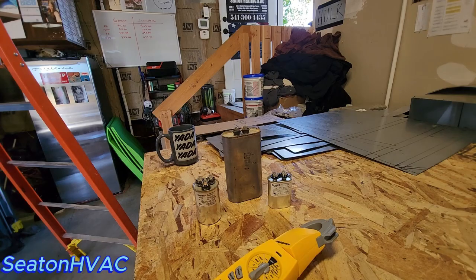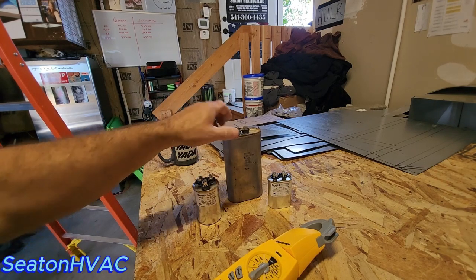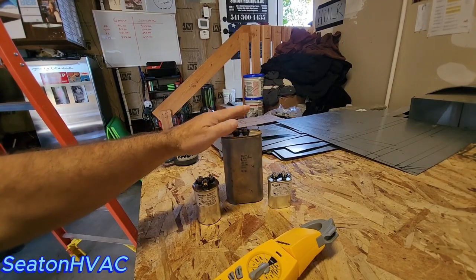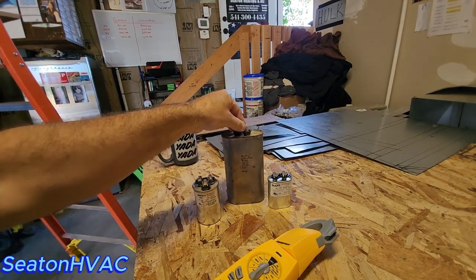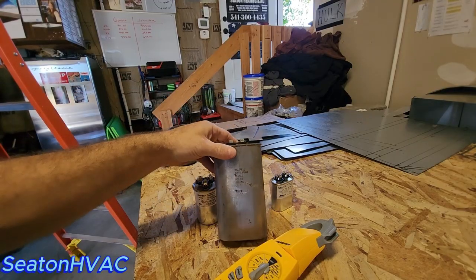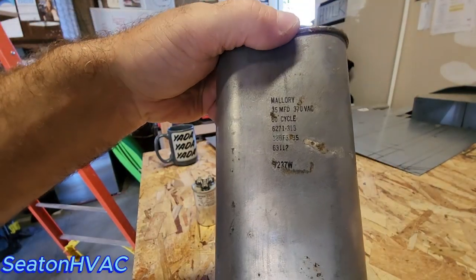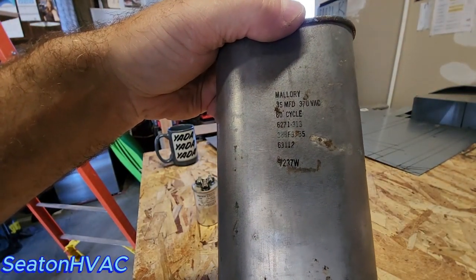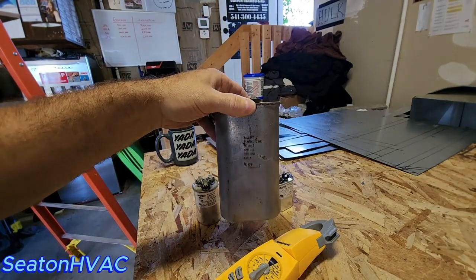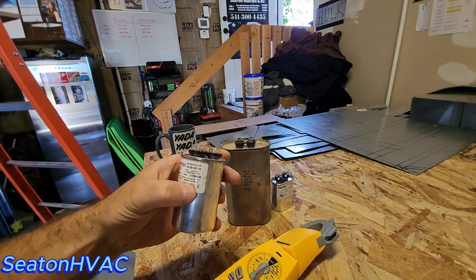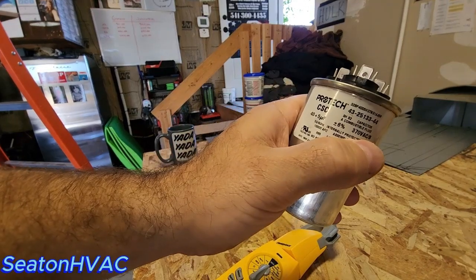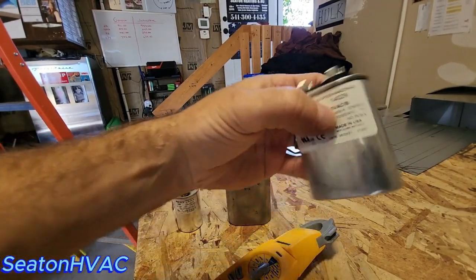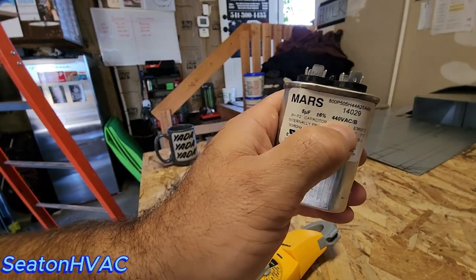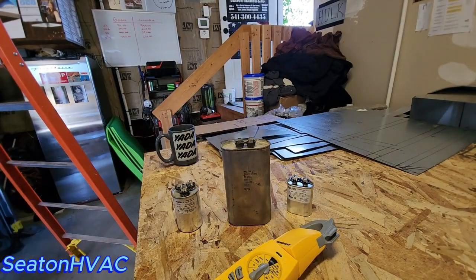Okay, let's start with the old capacitors here. So how do we test these guys out? And I was wrong, sorry, this wasn't a dual capacitor. This is just a compressor capacitor, an old Herm capacitor from a 52-year-old unit that I pulled out a while back. So you can see the numbers on that: 35 microfarads, 60 hertz, 370 VAC. Same way they make them today, except today they do them dual VAC on most of them. Actually, these Protech are 370 VAC, and these Mars are 440 VAC. So anyway, how do we test these?